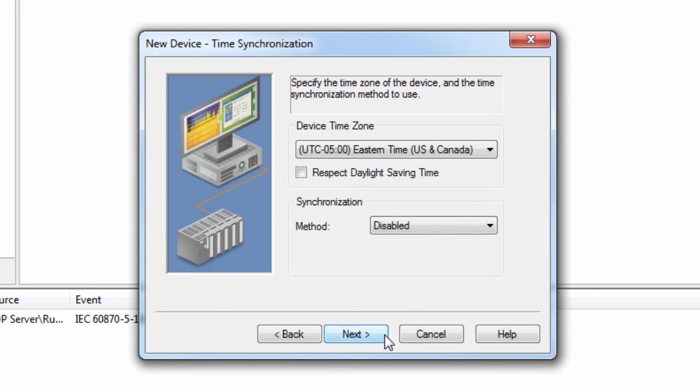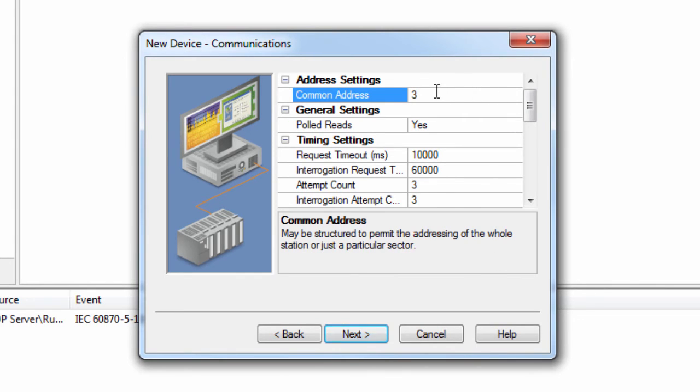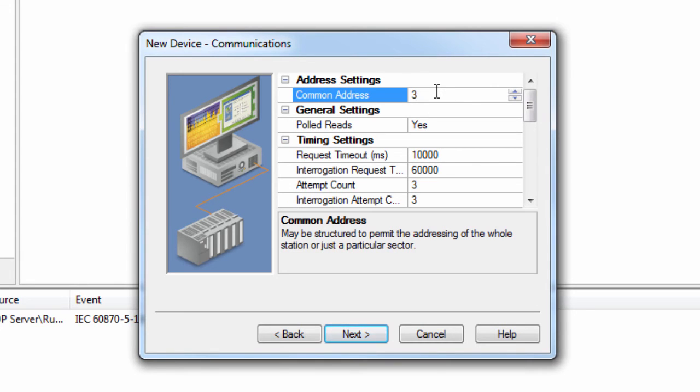Click Next to set the communication parameters. Most of these settings can be left at default, but I will highlight two significant ones. For the common address, you will need to enter the device or station address. The valid range is 0 to 254, or 65,534, depending on whether the common address size setting was set to 1 or 2 octets in the channel configuration. The default setting is 3. Devices within a channel must have unique common address pairs because the master must have unique sector references within a channel.